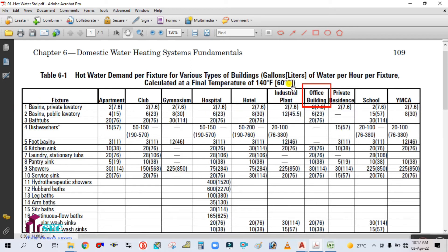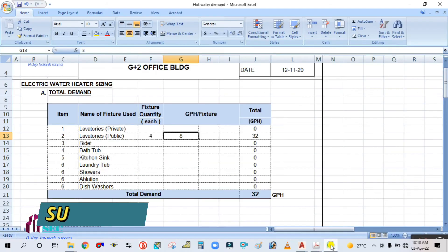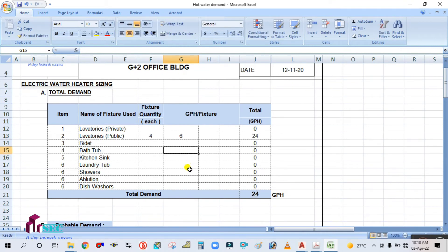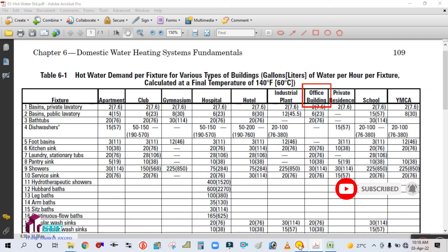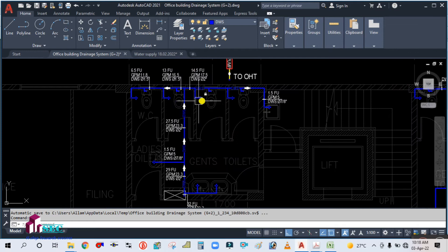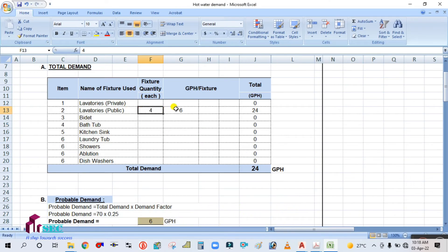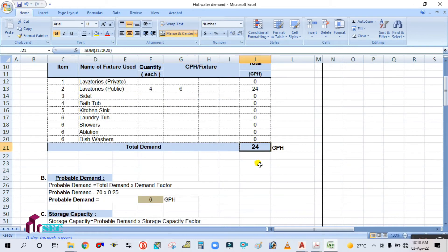In this table, two values are given: outside the bracket in gallons per hour per fixture, and inside the bracket in liters. We need gallons per hour per fixture. For office building, public lavatory, look it up — you will find 6 gallons per hour per fixture. Simply enter 6 here. There are no other fixtures requiring hot water — only lavatories. So with four lavatories at 6 GPH each, the total demand is 24 GPH.